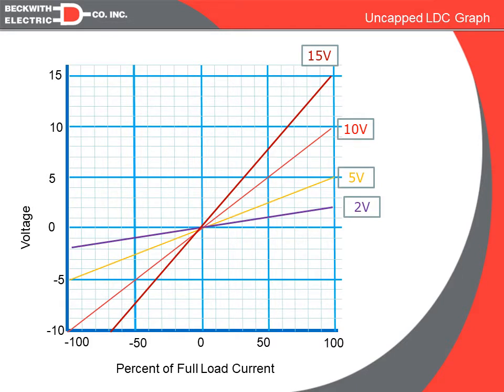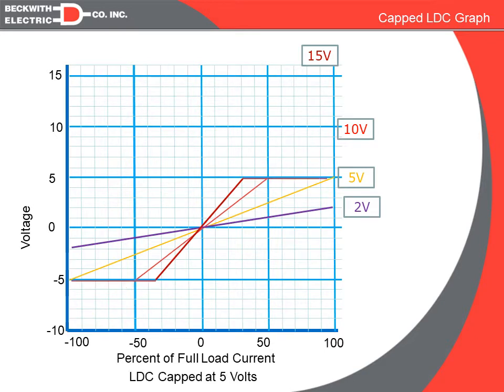If we cap the compensation at 5 volts, the slope of the 15-volt setting still applies, but once we reach 5 volts it will not apply any additional compensation in either direction. The idea of capped compensation is that it allows a higher R and X value for a steeper slope, but still provides insurance that no matter what the load does, no more than a set number of volts of total compensation is applied. The bus voltage will never be more than five volts higher or lower than the band center.